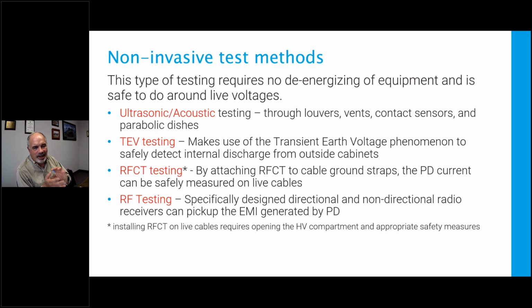RFCT testing, this kind of dances the line between invasive and non-invasive. We take a split core radio frequency current transformer called an RFCT or an HFCT, the same thing, and we attach it to the cable ground straps. Some people put them on conductors. I don't like them on conductors. Put them on the ground straps where they're inherently safe. Put them right down by the ground bar and bring your connectors out to a safe spot. Now I can test that cable anytime I want. I don't need to take an outage. I can test it every day if I want, and I can trend it if I want. I can put full-time monitoring on. I can test it once every 3 years without taking an outage. So installing those, once they're installed, then that's really non-invasive.